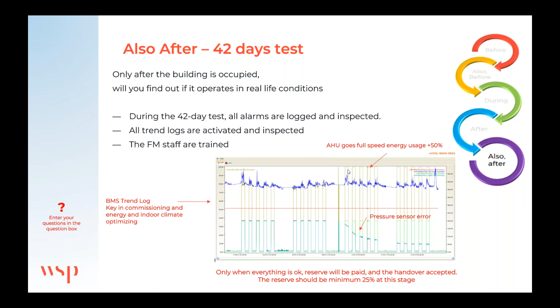And the reason for that is that the sensor is broken. But you cannot find this out just by looking at the system, because it sounds the same. You need a tool like trend logs to investigate this. This is actually one of the most important parts of a building management system, and something that needs to be part of the commissioning process.